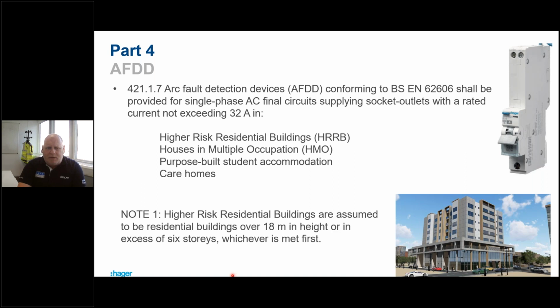Okay, next, part 4, arc fault detection devices. So this is where one of the biggest changes has happened. In the 18th edition, AFDDs were recommended for all final circuits, recommendation only. They've gone away, they've looked at this regulation and they've come back with this one. Arc fault detection devices shall be provided, so it's the word shall, so we must do this, for a single phase AC final circuit supplying socket outlets with a rated current not exceeding 32 amps.